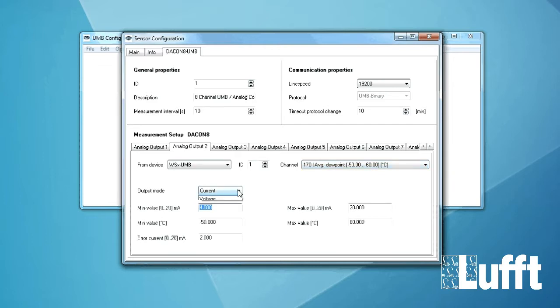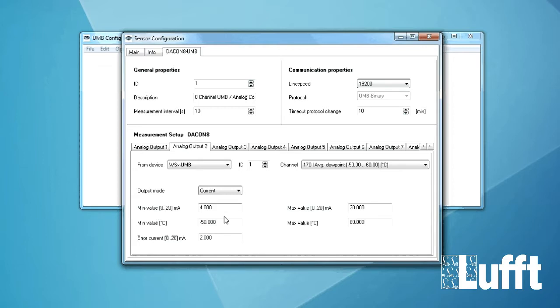Again WSX ID1 and then we can for example map the channel 170 which is the average dew point for example. The same thing. We choose the output mode of the current. Then minimum value. Maximum value. Minimum value in Celsius degree. Maximum value in Celsius degree. And the error current. Same thing.